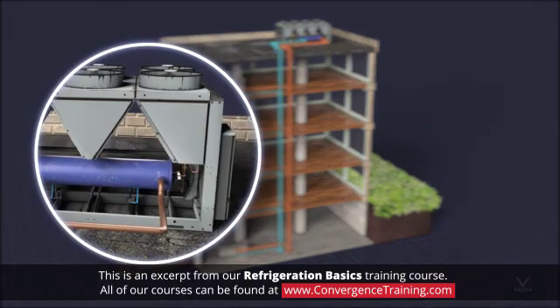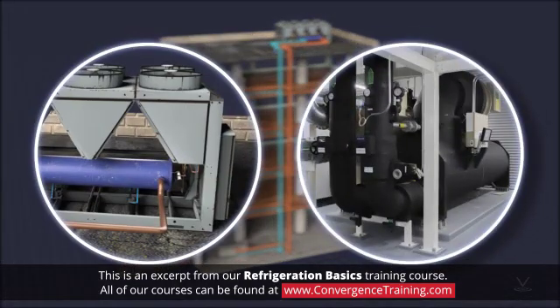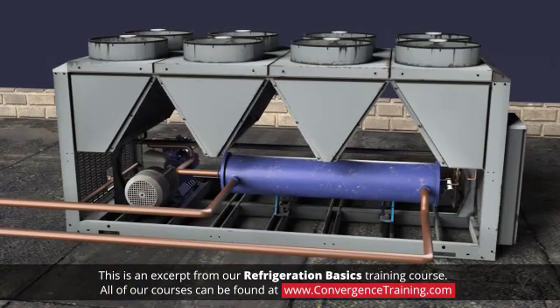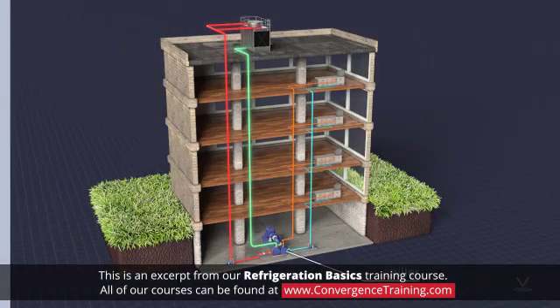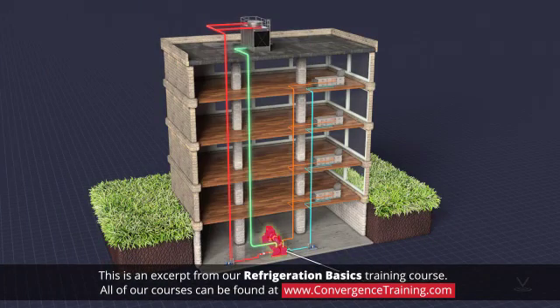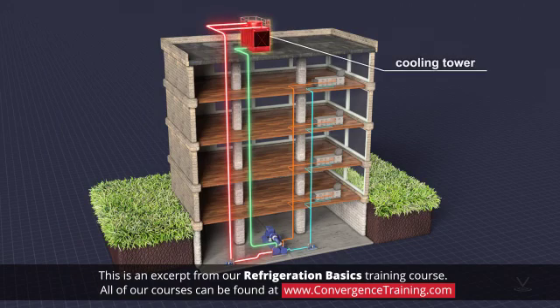Chillers can be air-cooled or water-cooled. Air-cooled chillers release thermal energy from the refrigerant in the condenser to the outside air, while water-cooled chillers release thermal energy from the refrigerant in the condenser to a cooling water loop, which is pumped to a cooling tower where it is cooled for reuse.